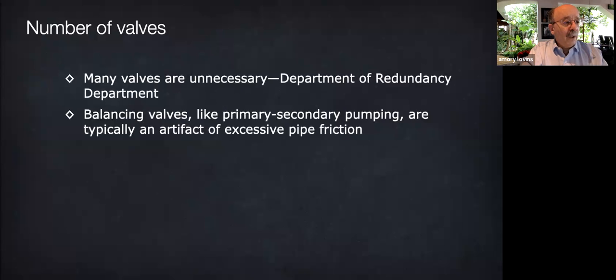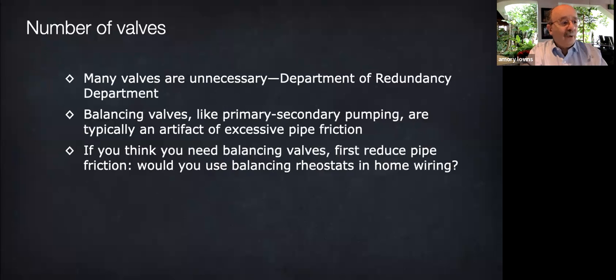Now, some valves are necessary, for example, to isolate sections of piping for repair or for emergency shutoff, but we shouldn't use valves to reduce and adjust flow. We should let the electronic motor drives do that by changing the pump speed and hence the flow. Lots of valves are unnecessary. Balancing valves are typically a sign of excessive pipe friction. You know, you wouldn't use balancing rheostats in your home wiring to even out the current flows.